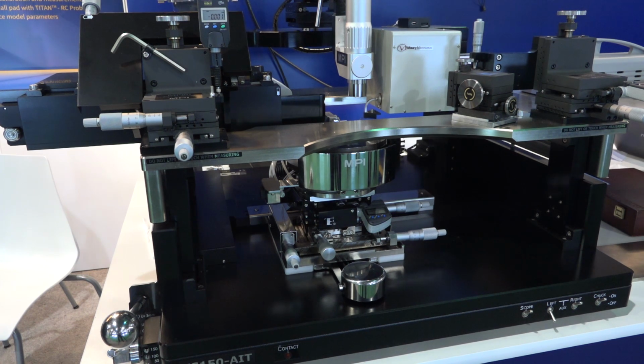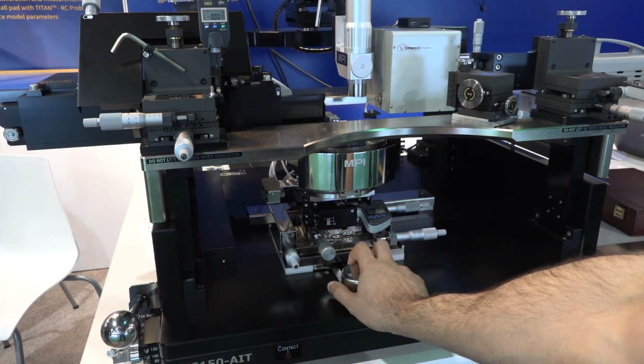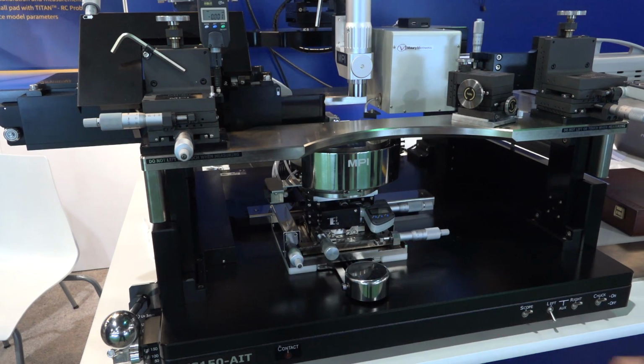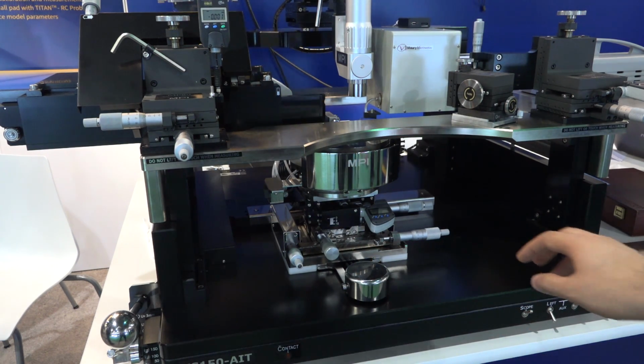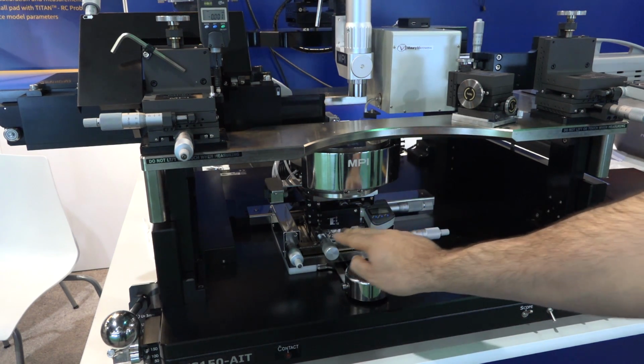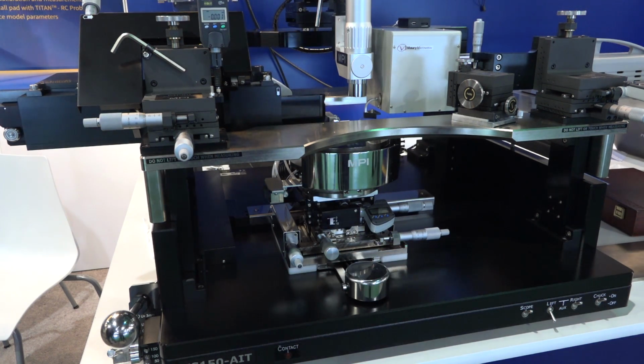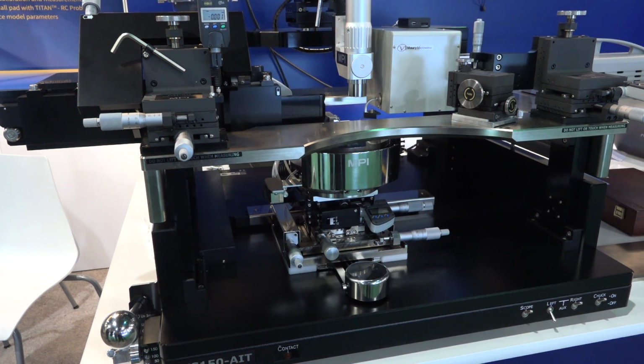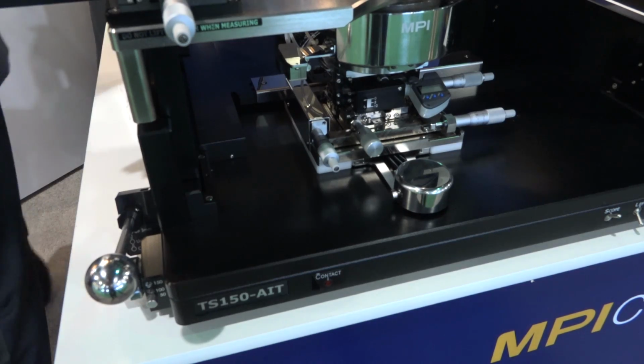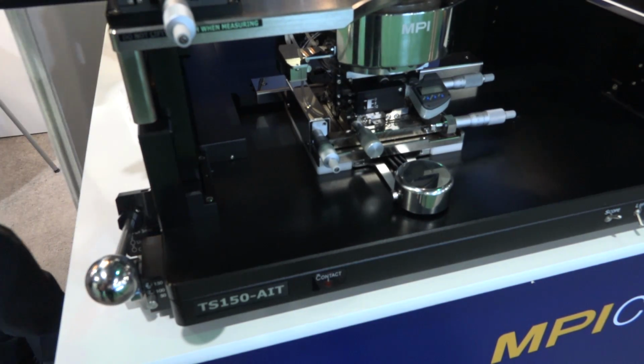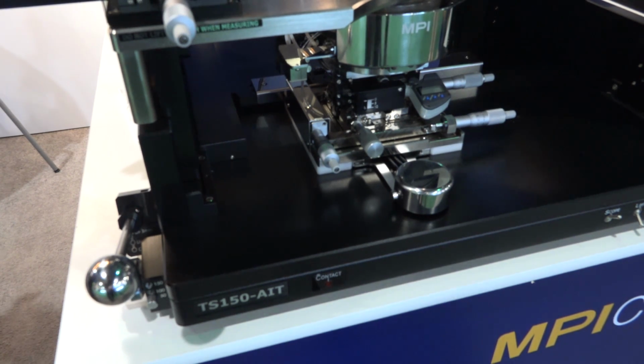And once you're satisfied with that, you can go ahead and land the probes at different precisions and at different levels, and then the instrument would lock this and wouldn't allow you to move the station anymore, which would protect your probes, of course. Now there are very fine movements, which you can see with these knobs over here. Once the station is locked, then you can do very fine adjustments and movements after that. So let me also show you this nice design they have here for landing the probe. So right now the probes are not landed.